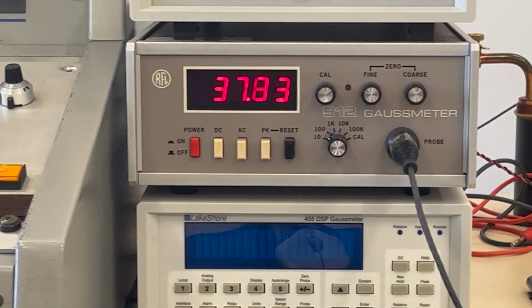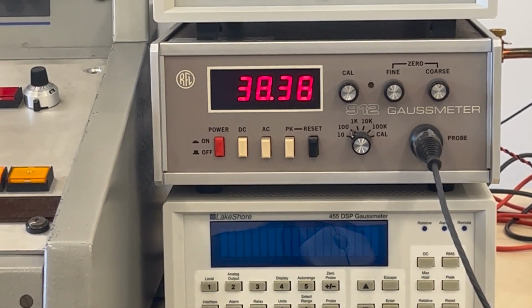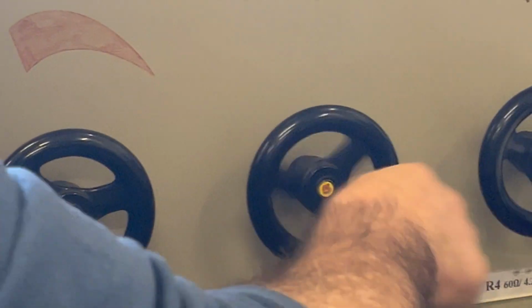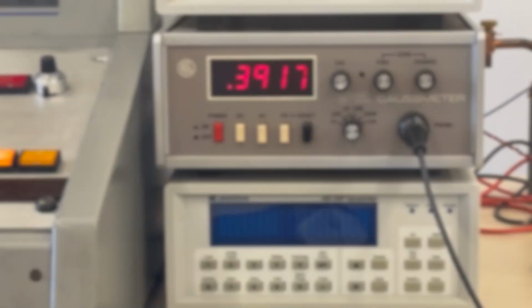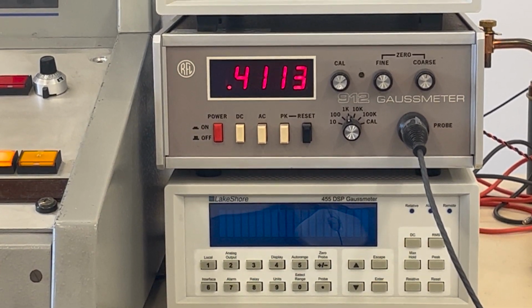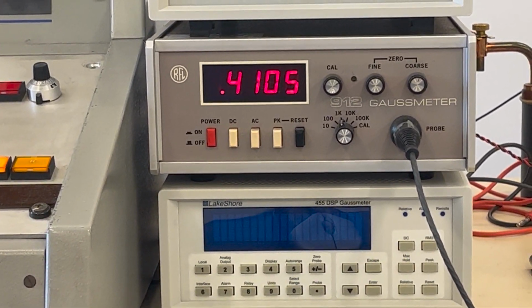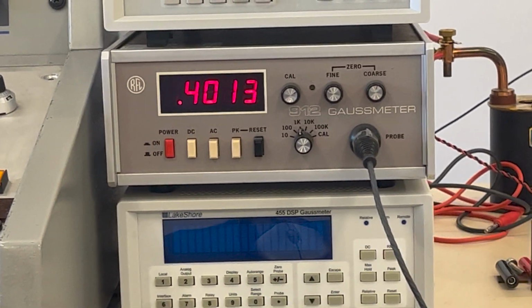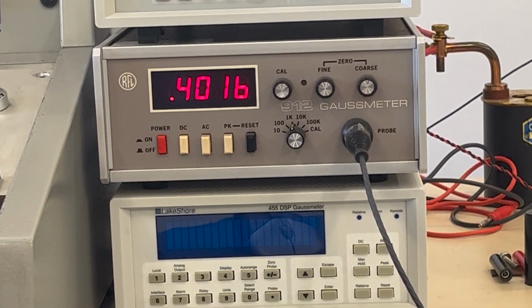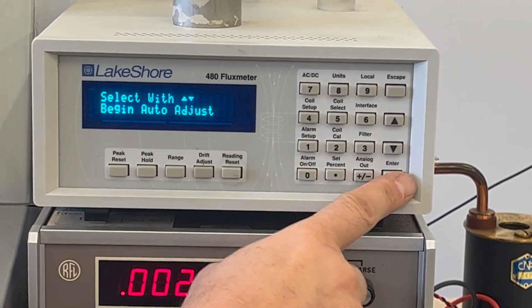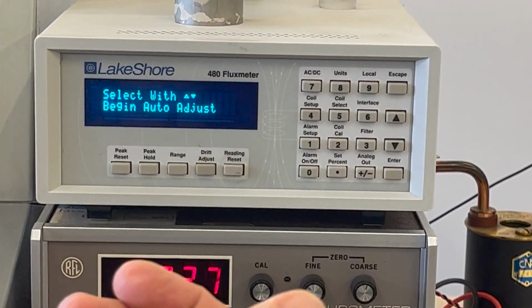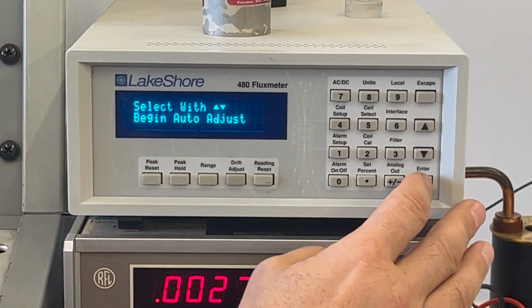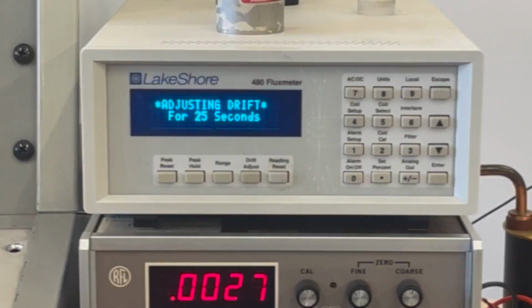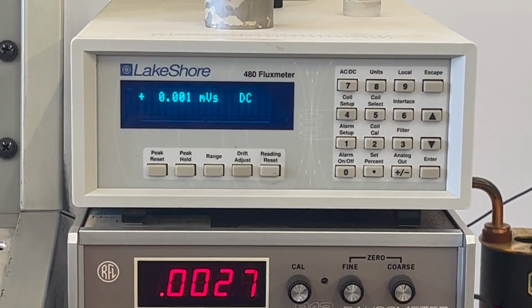The magnetization curve is measured one point at a time. As an example, our first field point is of the order of 400 Oersted. So we regulate the current that flows into the yoke in order to reach the desired field value. The flux meter, since it is an integrator, is subject to drifts. For this reason, it is important to compensate for these drifts in order to have a stable measurement.